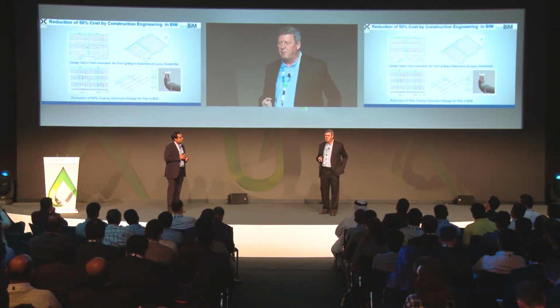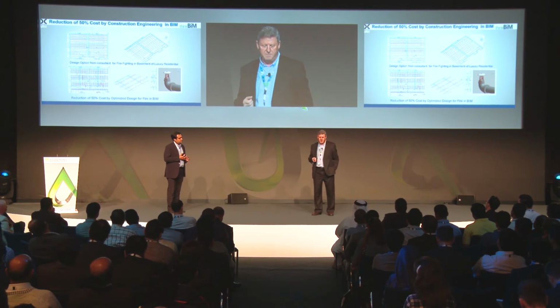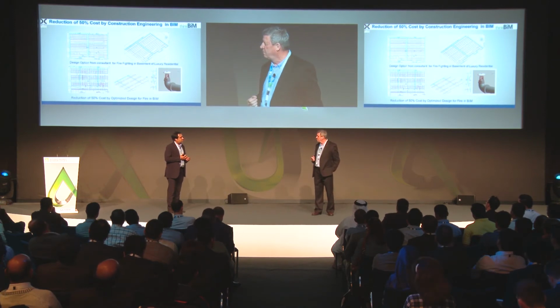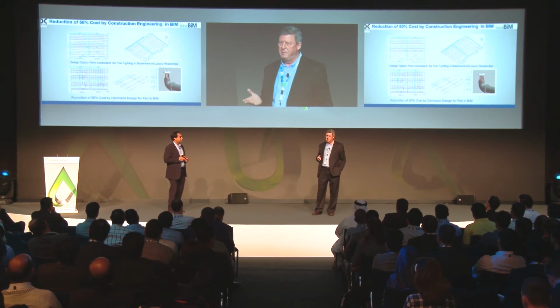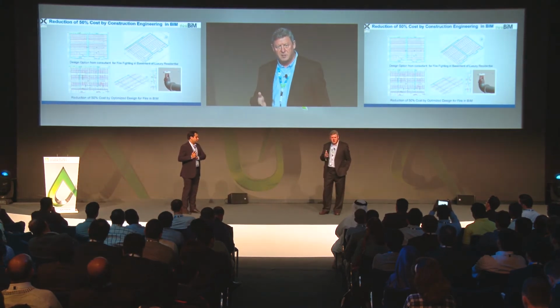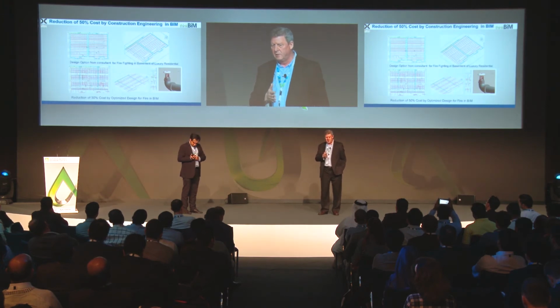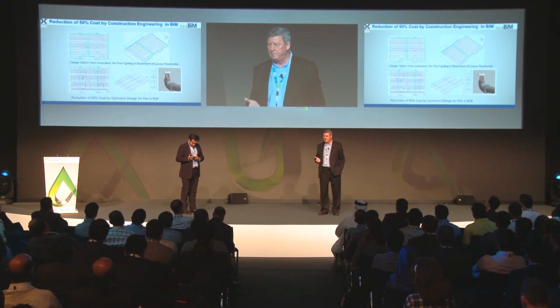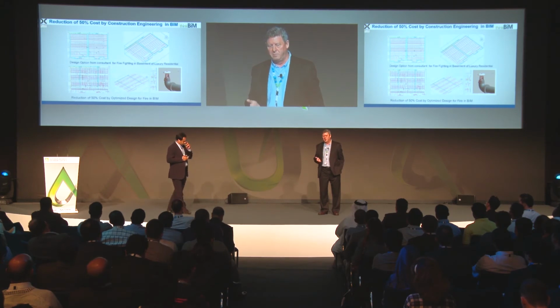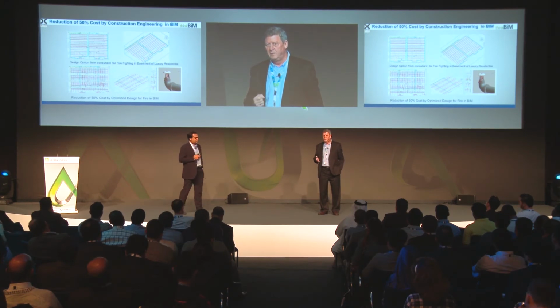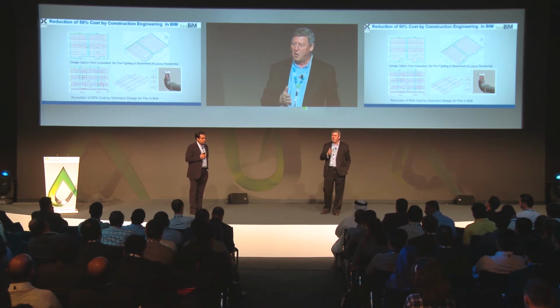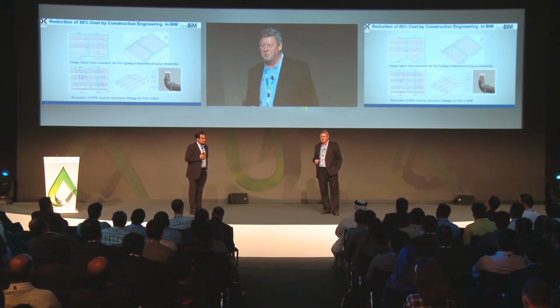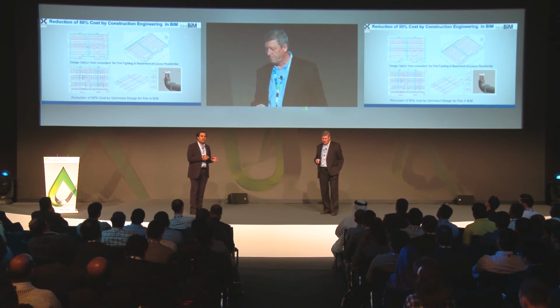This is a simple example of a sprinkler range pipe. The basement of this building is about 3 million square feet. We took a simple zone of sprinklers—the original design is shown on top. We redesigned it with a different distribution and cut the sprinkler cost for each module by 50%. That's not much over a single zone, but multiplied out over 3 million square feet, it's enormous. The reason we could do that was because when everything is done in BIM, you can query the data.